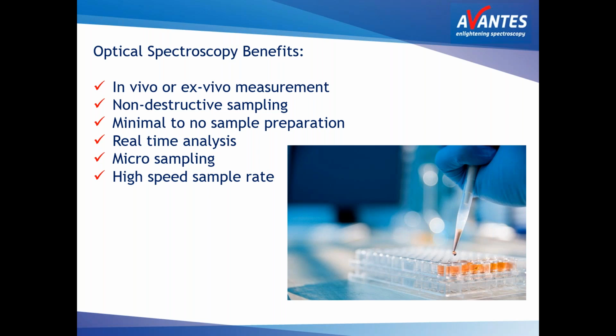And finally, high-speed sampling rate. And I've alluded to this previously, that because these instruments can acquire data in millisecond timescales, even microsecond timescales, it's not unreasonable to think of sampling at a rate of seconds or a few seconds, even with multiple averages to provide improvements in signal to noise.